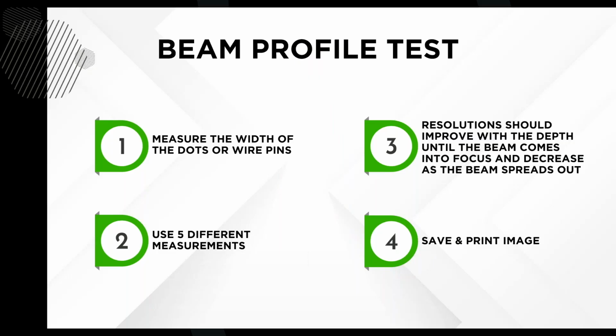This one, measure the width of the dots or the wire pins. You use 5 different measurements. The resolution should improve with the depth until the beam comes into focus and decrease as the beam spreads out. And then we'd save and print this image.